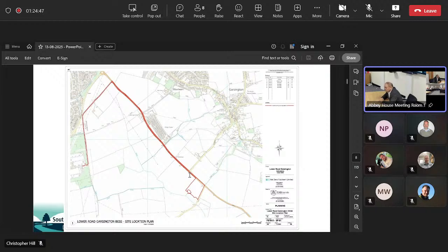Could you explain then why this proposal isn't adjacent to a renewable energy generating site such as solar or wind, and why it has to be put in the middle of a completely open space in the green belt? Sure. So there is no technical requirement for a grid scale battery installation like this one to be located next door to either the generator of the energy, a solar farm or whatever it may be, or indeed the grid connection point, as in a substation. The reason this location has been selected for this planning application is a result of the multi-layered site analysis and site finding process which we go through.